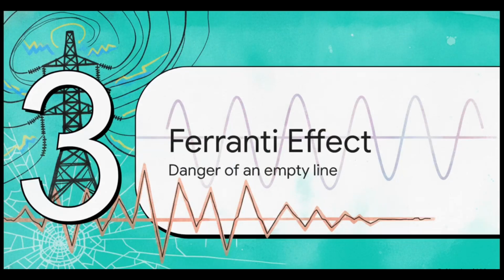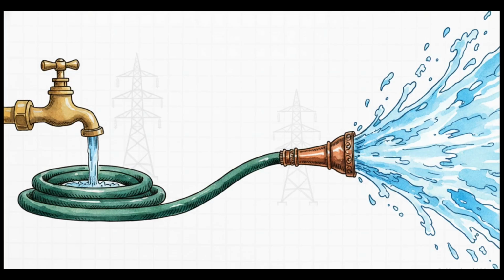Moving on to Section 3, the Ferranti Effect, the danger of an empty line. This is a totally different, counterintuitive threat to the grid. This one is a complete mindbender. Get this. The voltage at the receiving end becomes higher than the voltage at the sending end. Imagine turning on your garden hose and the water pressure coming out of the nozzle is somehow way stronger than the pressure back at the spigot. That is essentially the Ferranti effect.